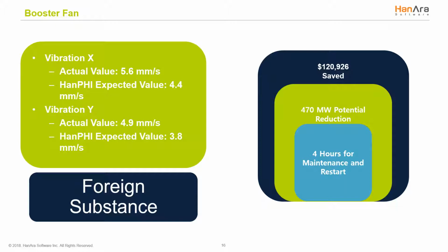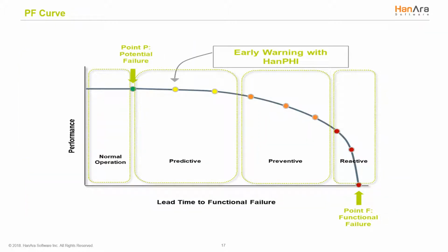After HanPHI's early warnings, the site tested the fan open ratio and determined that there was a foreign substance on one of the fan pitch blades. After eliminating the foreign substance, the fan stabilized. Those are just a few real-world examples from our customers regarding how they use HanPHI and how it reduces their unnecessary maintenance activities. This occurs because HanPHI provides warnings early enough to take the proper action. Looking at the standard PF curve, HanPHI gives plants, even without specialists analyzing the data, an early warning of a potential failure.